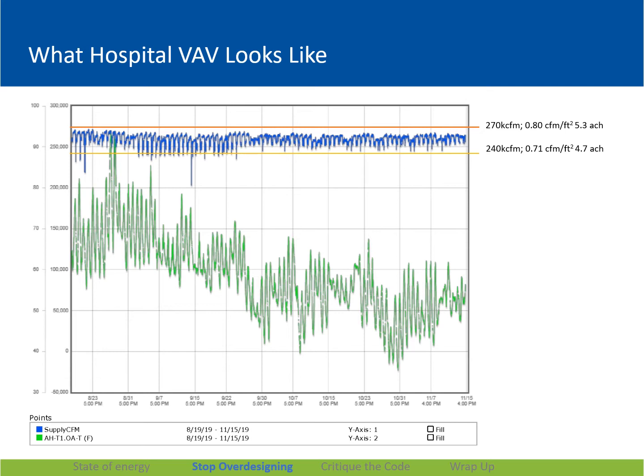The lowest number on this graph is 240,000 CFM, which is 0.7 CFM per square foot, or 5 air changes per hour. And the reason I'm showing you this picture is because this is the best one that I've found. Out of our 32 hospitals, this is the best VAV system that I've found. So we have the high, the peak demand at 90 degrees in the middle of the day, and then the low, the overnight demand when it's 60 or 75 or 70 degrees outside. In this system, the difference between the peak and the low is 15%. That's a 15% turn down. Now, I have a technical term for that. It's called, you might as well not do VAV, or this is really shitty VAV.